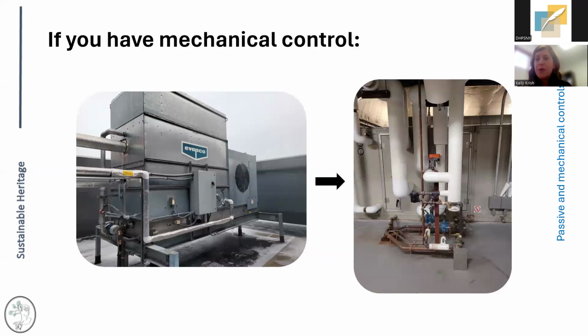Okay. Now we'll move more into if you have mechanical control. There's some key information that you want to get to be able to understand what dew point you're capable of achieving and whether the system has been able to do that successfully. There's a couple of ways that you can get this information. One would be through the documentation related to the HVAC system. Often there's as-builts that would list what the cooling coil is capable of achieving. There can be gauges on the sides of the mechanical system that show what temperature the chilled water is being supplied at. You can talk to your facilities department, who should be able to provide you with information about the dew point of the mechanical system, as well as for the chilled water, or you can monitor. So those are really the 4 ways to get at what your mechanical system is capable of providing.